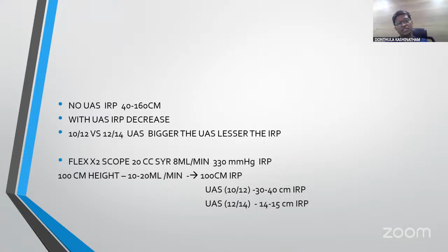So as a rough guide, if you put 100 centimeter height, approximately 10 to 20 ml per minute flow will be there. Without an access sheath, the pressure will be 100 centimeters. With an access sheath of 10 to 12, the pressure will drop drastically to 30 to 40 centimeters. If your access sheath is 12 to 14 size, it is around 14 to 15 centimeters pressure.